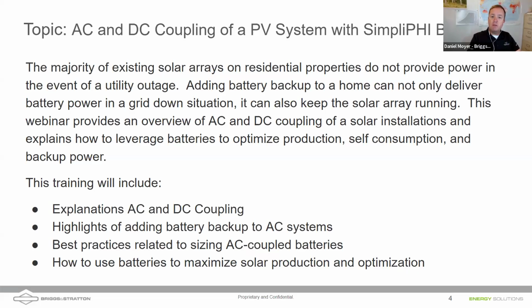So it's a great way to retrofit existing systems that don't require you to get the ladder out and go up on the roof. We're going to leave the microinverters and the string inverters in place, and add usually a hybrid inverter and a battery, then bring that AC coupled solar in.